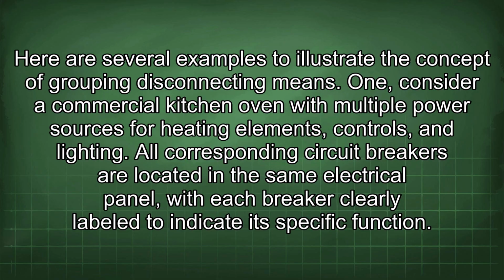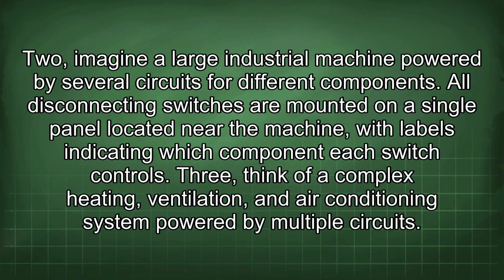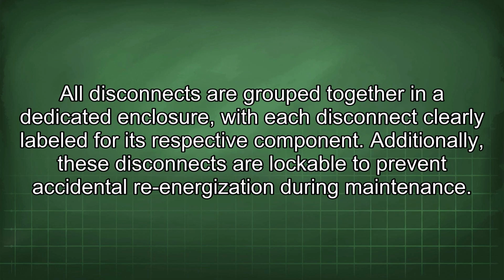Here are several examples to illustrate the concept of grouping disconnecting means. 1. Consider a commercial kitchen oven with multiple power sources for heating elements, controls, and lighting. All corresponding circuit breakers are located in the same electrical panel, with each breaker clearly labeled to indicate its specific function. 2. Imagine a large industrial machine powered by several circuits for different components. All disconnecting switches are mounted on a single panel located near the machine, with labels indicating which component each switch controls. 3. Think of a complex heating, ventilation, and air conditioning system powered by multiple circuits. All disconnects are grouped together in a dedicated enclosure, with each disconnect clearly labeled for its respective component. Additionally, these disconnects are lockable to prevent accidental re-energization during maintenance.